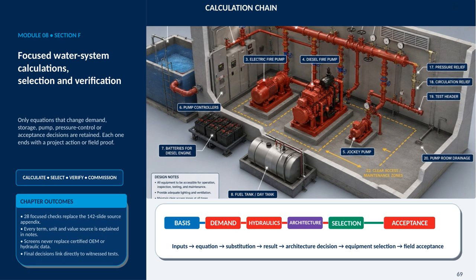We begin by establishing the basis, then quantify demand, evaluate hydraulics, define the system architecture, select equipment, and finally confirm performance through acceptance testing. In practice, that means moving from inputs to an equation, to substituted values, to a result, and then to the decision that result supports. Every term, unit, and value source should be explained in the notes, so the work can be reviewed and reproduced. It is also important to keep the boundary clear. Screens and calculations do not replace certified manufacturer data or hydraulic data. They support selection, but the final decision must connect directly to witnessed field tests. The overall sequence is simple: calculate, select, verify, and commission.